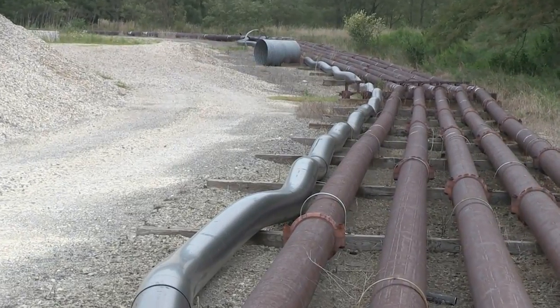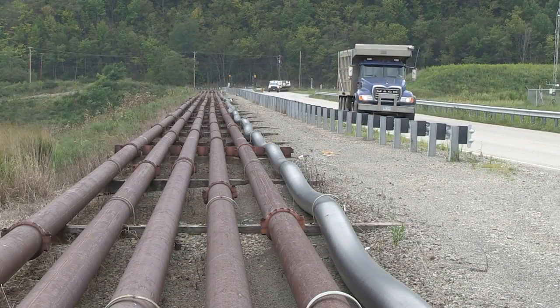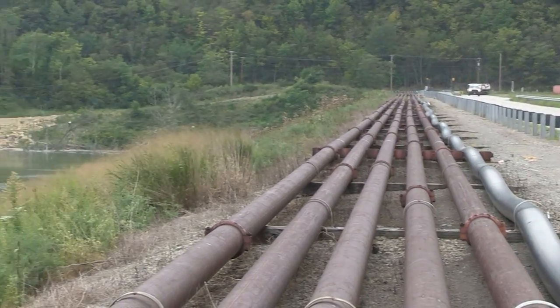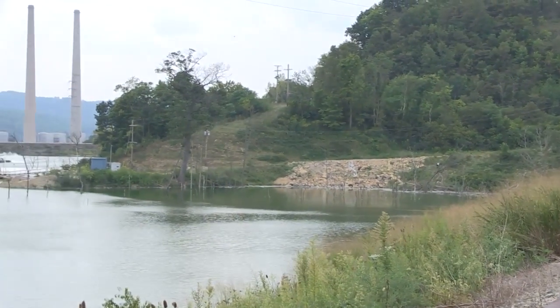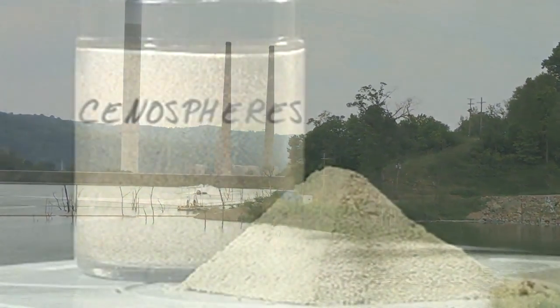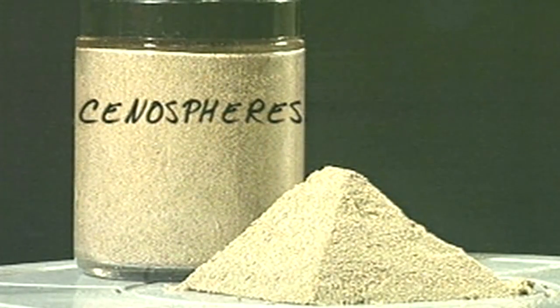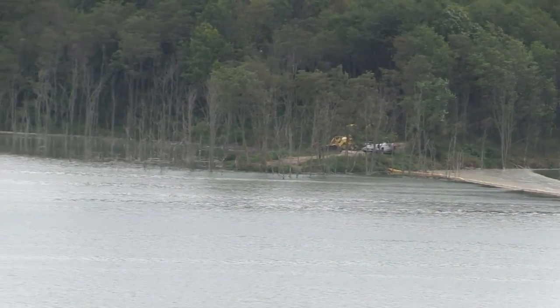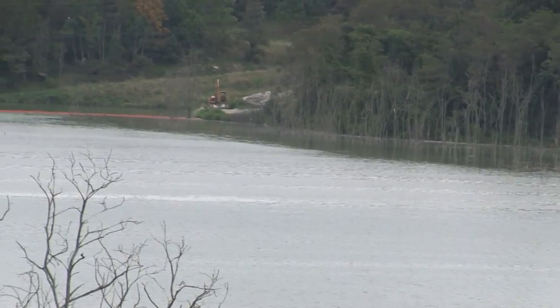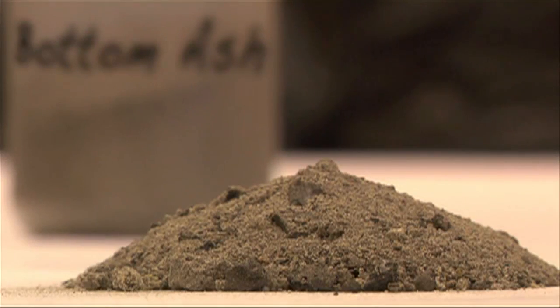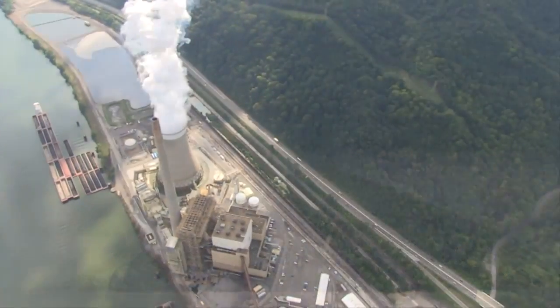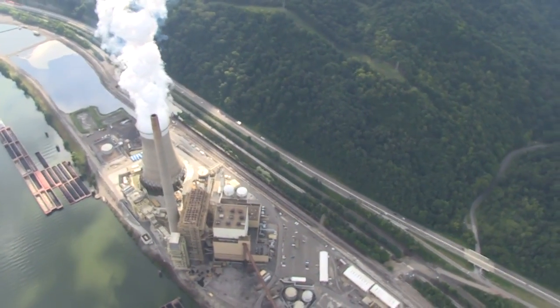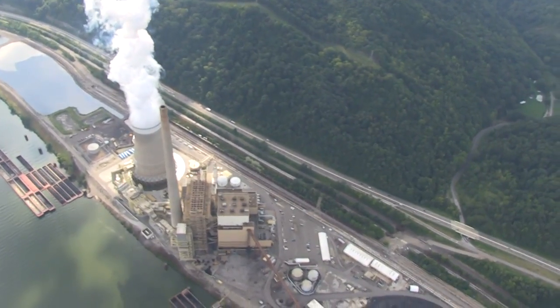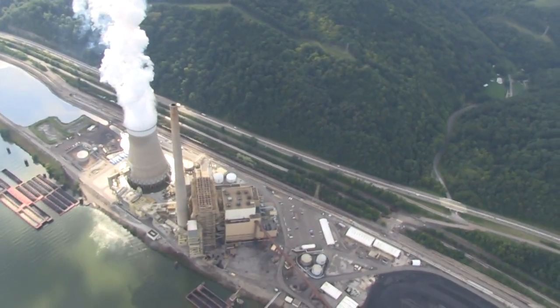So what happens to the more than 450,000 tons of fly ash that's collected by the precipitators each year? It's mixed with water and pumped in large pipes up to a collecting pond for disposal. Some of the particles in the fly ash, called cenospheres, have commercial applications and are harvested for use as fill materials in the manufacturing of plastics and space-age ceramics. The other 20% of the ash produced, which falls to the bottom of the boilers, is called bottom ash. It's stored in ponds next to Unit 3 and is sold as an ingredient in road construction material and cinder blocks, or for snow and ice control on highways.